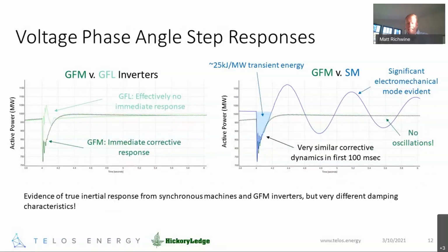Okay, moving on to the phase angle step responses. First we're going to look at a negative phase angle jump. Again, on the grid forming versus the grid following inverters, you can see that active power from the grid forming inverter is reduced quickly, and then it moves back to its pre-fault level in about 200 milliseconds. In contrast, the dynamics of the GFL are quite a bit different. There's a disturbance of sorts, but in general, the power doesn't change much, and it kind of cruises through the event because it's intending to regulate power to the extent that it can.